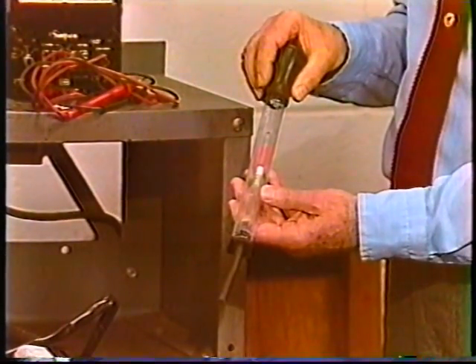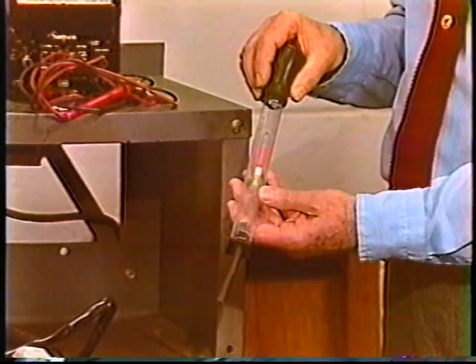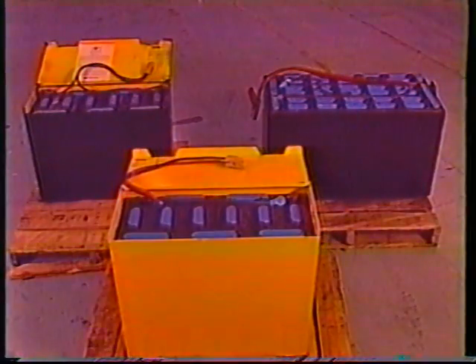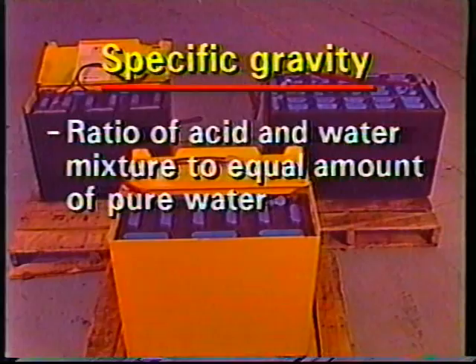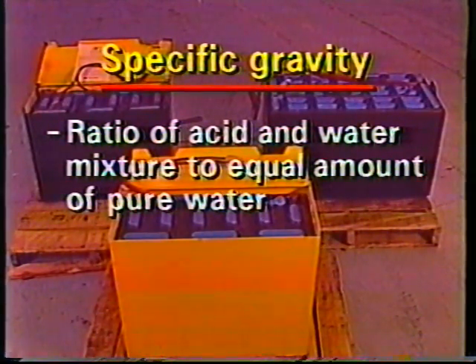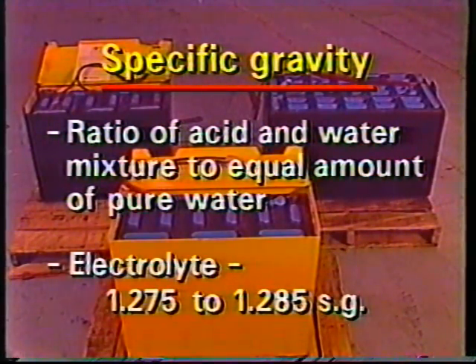However, measuring the specific gravity of a cell with a hydrometer is the most accurate measure of battery discharge. The specific gravity of a cell is the ratio of the weight of the sulfuric acid and water mixture in a cell to an equal amount of pure water at a specified temperature. Pure water has a specific gravity of 1.0. In a fully charged cell, the electrolyte normally has a specific gravity of 1.275 to 1.285. We'll learn how to measure specific gravity with a hydrometer in part 2 of this training series.